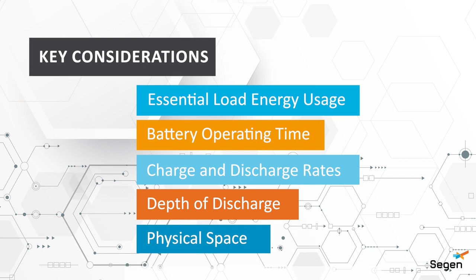Calculating the amount of surplus energy available for a battery storage system requires an analysis of the hourly energy generation throughout the year and the expected hourly energy use of the property. Some key considerations include essential load energy usage, battery operating time, charge and discharge rates of the equipment, depth of discharge, and the physical space available in the property.